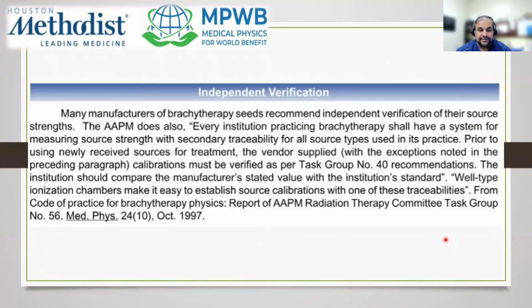This is taken from the Brachytherapy Source Calibration Manual, distributed by the company CDOS, and it says the exact same thing. Every institution shall have a system for measuring the source strength with secondary traceability.